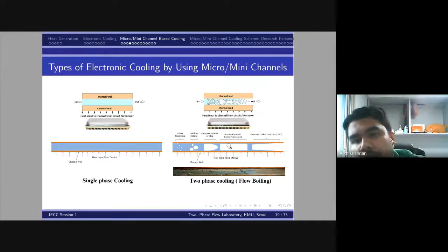So in this way, two categorizations we can use to adopt mini or micro channel cooling: one is single phase flow and the other is two phase flow. Nowadays most cooling strategies belong to this flow boiling, that is two phase cooling. They are adopted because both latent heat and sensible heat can be absorbed from the processor in order to cool it effectively. But a lot of issues are also associated with that, which we will generalize later.